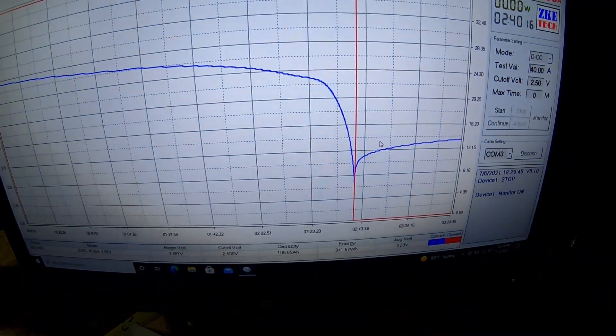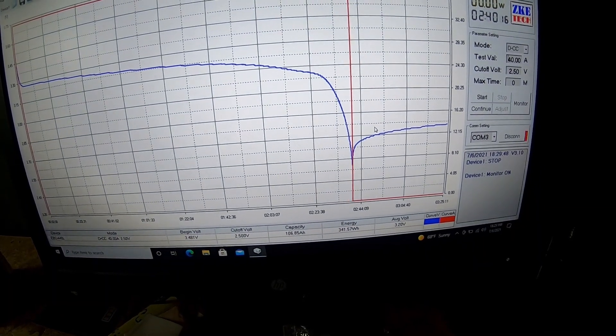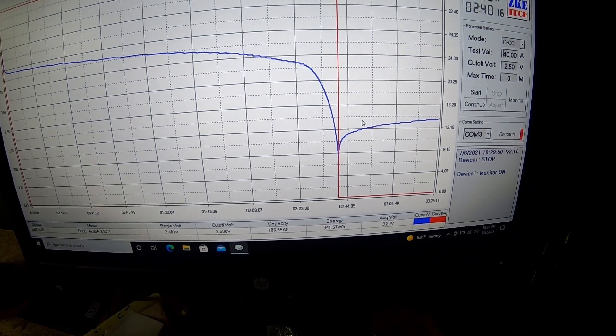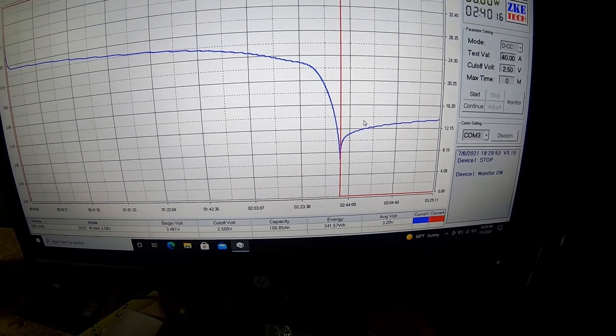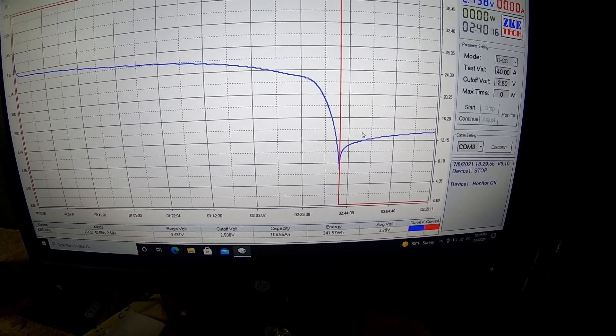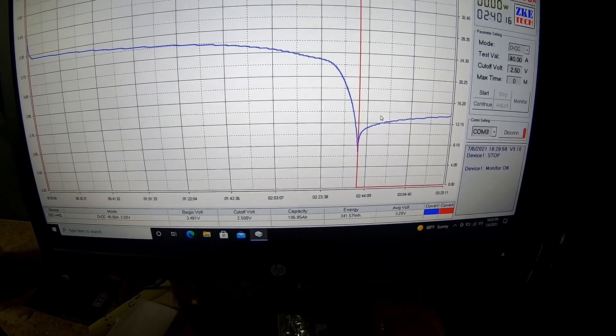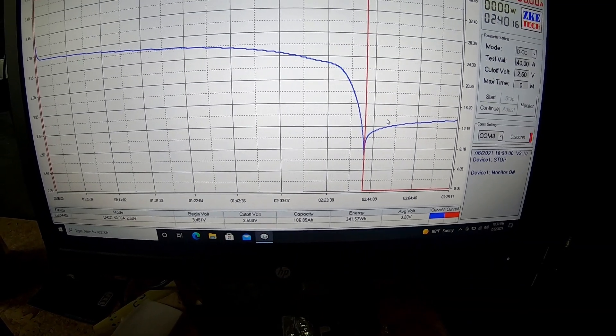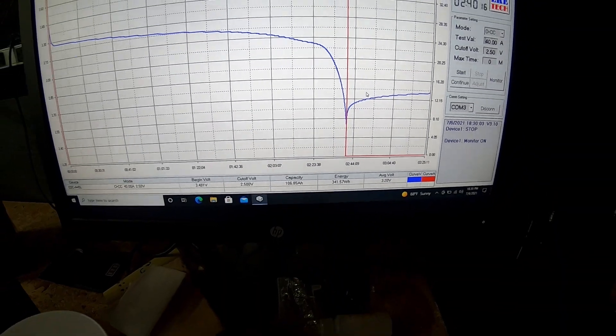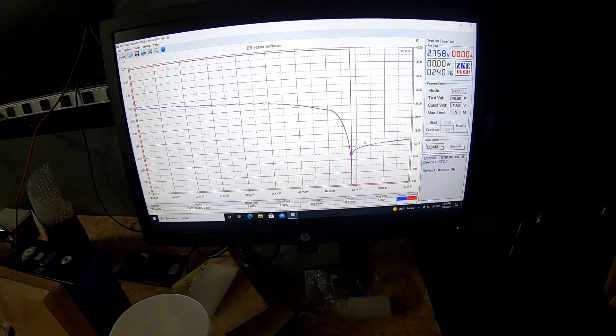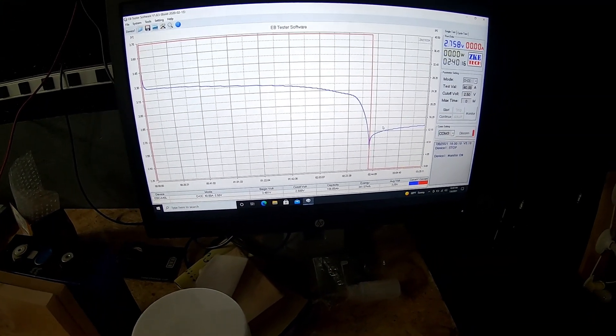And welcome back. As promised, we just finished our discharge test of this cell. As you can see there, we stopped at our target voltage of 2.5 volts just shy of two hours. Looks like two hours and 40 minutes, and we pulled 106.85 amp hours with the capacity, which is, you know, to me a great result off of a 100 amp hour battery.